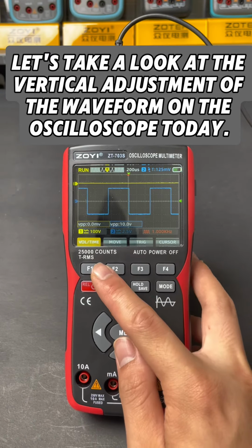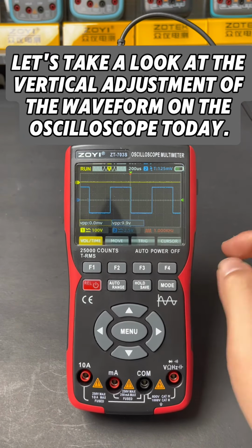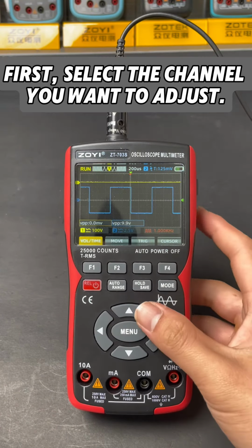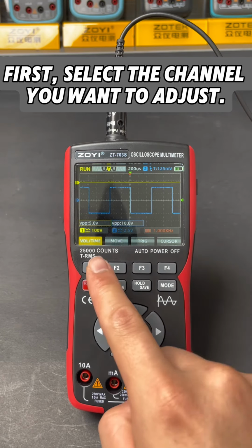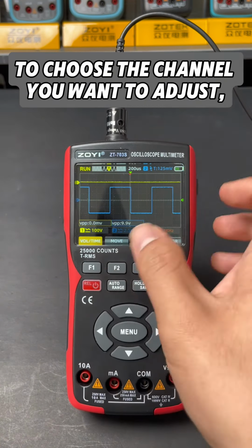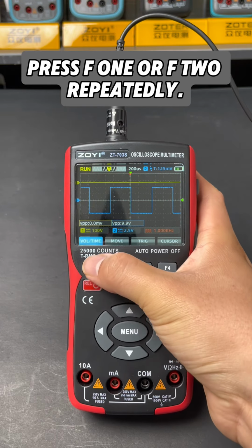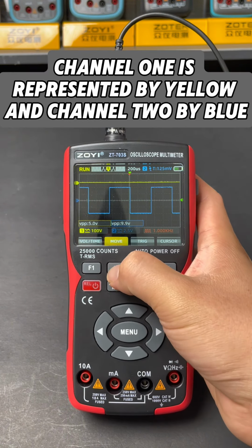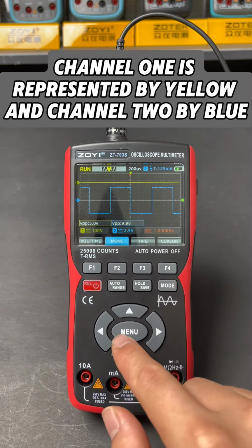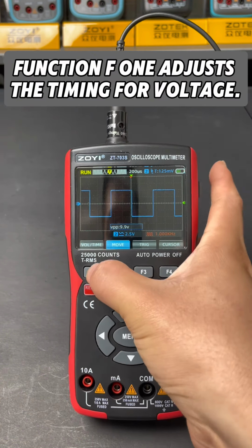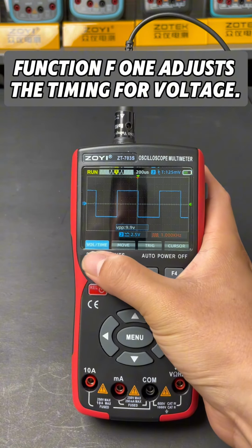Let's take a look at the vertical adjustment of the waveform on the oscilloscope today. First, select the channel you want to adjust. To choose the channel you want to adjust, press F1 or F2 repeatedly. Channel 1 is represented by yellow and channel 2 by blue. Function F1 adjusts the timing for voltage.